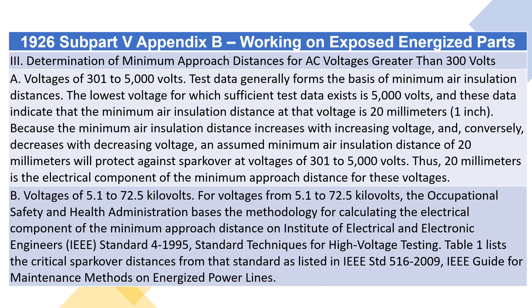Determination of minimum approach distances for AC voltages greater than 300 volts. Voltages of 301 to 5000 volts: test data generally forms the basis of minimum air insulation distances. The lowest voltage for which sufficient test data exists is 5000 volts, and these data indicate that the minimum air insulation distance at that voltage is 20 mm (1 inch). Because the minimum air insulation distance increases with increasing voltage and decreases with decreasing voltage, an assumed minimum air insulation distance of 20 mm will protect against sparkover at voltages of 301 to 5000 volts. Thus, 20 mm is the electrical component of the minimum approach distance for these voltages.